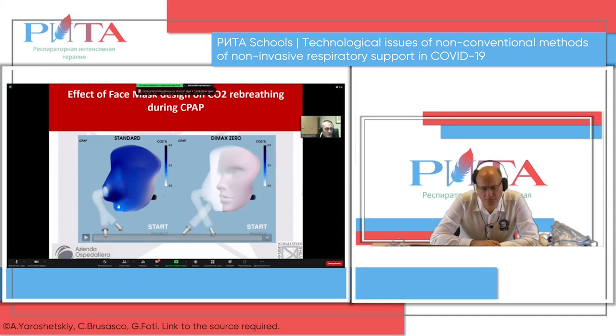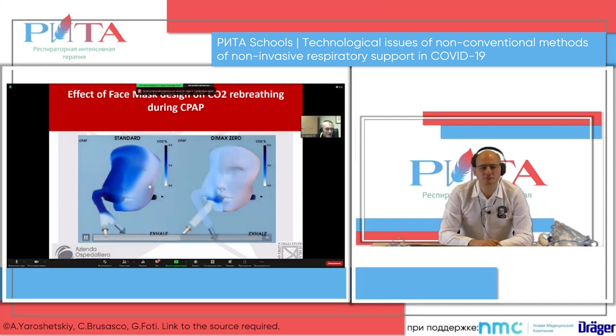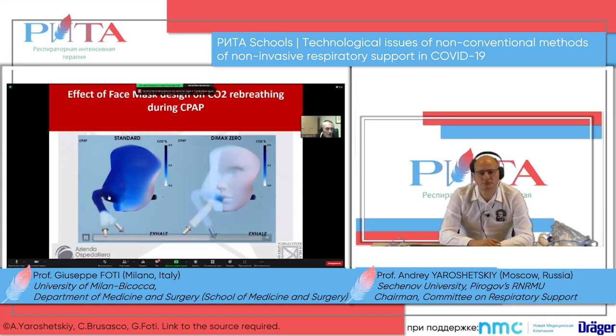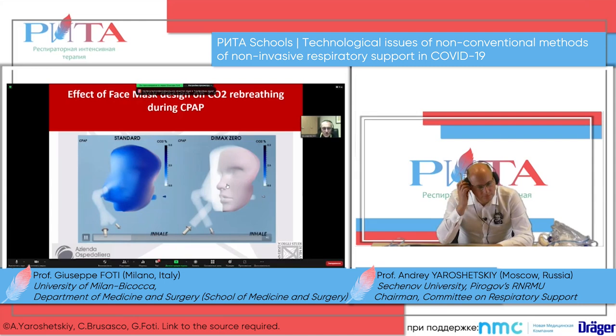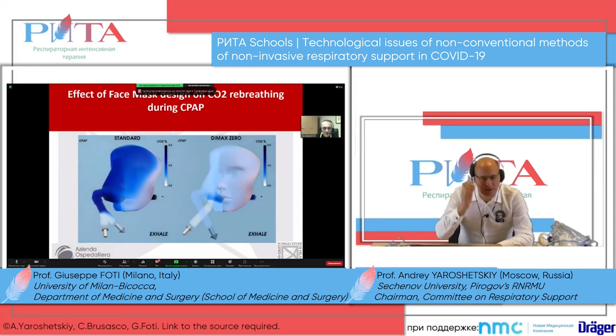The principle is very simple. Instead of having only one hole, where you have inspiration then expiration, you have inspiration from this side and expiration from this side. Look at what happens, the blue is the CO2. This is inspiration, now the patient expires. In one case, CO2 accumulates inside; in this case, because there is a continuous fresh flow of gases, the CO2 inside the mask is washed out. Did you see the point?